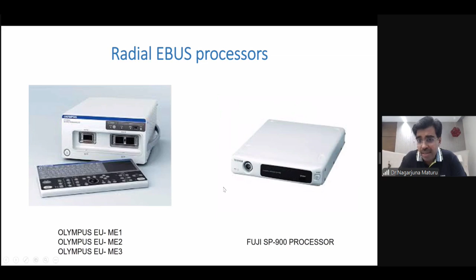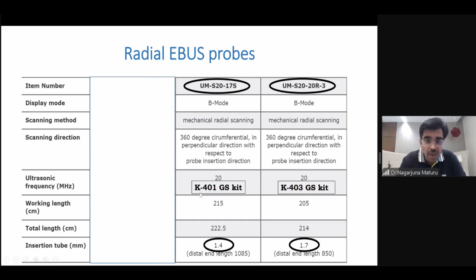Now coming to the probes. Olympus has two radial EBUS probes, the thinner and the thicker. For those who want the technical terms, they are 17S and 20R. 17S has a 1.4 mm diameter, and 20R has a 1.7 mm diameter. Both have 20 megahertz frequency. This is different from linear EBUS, where frequencies vary from 5 to 15. Radial EBUS has a higher frequency, so lesser depth of penetration. All radial EBUS probes have 20 megahertz. Each probe has a compatible guide sheath kit: 17S is compatible with 401, and 20R with 403. I will talk about it.